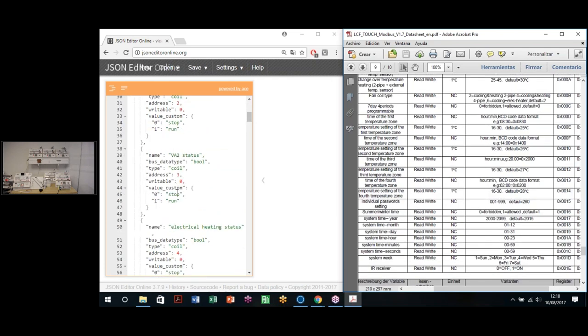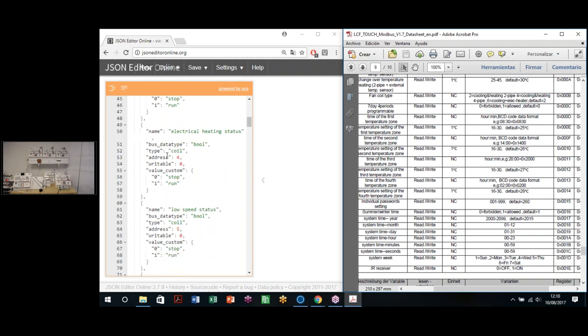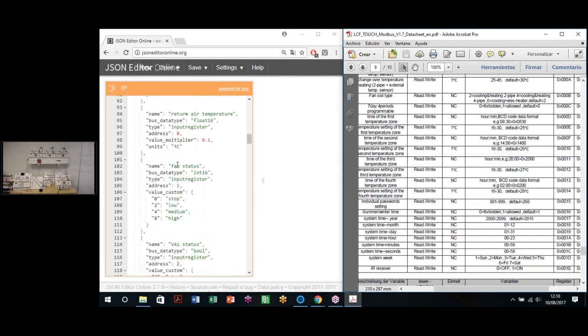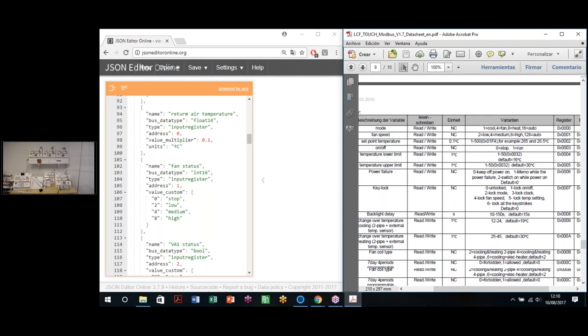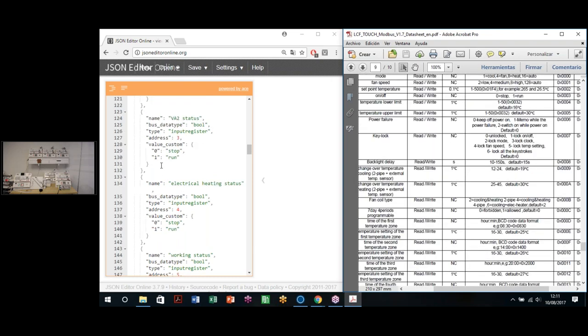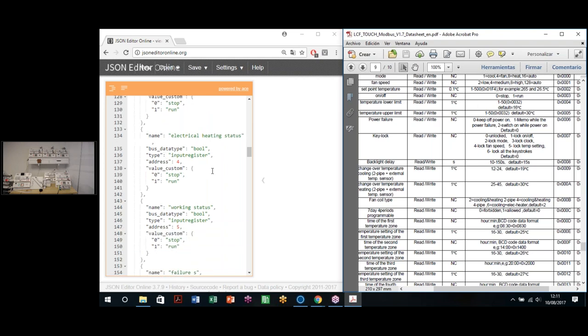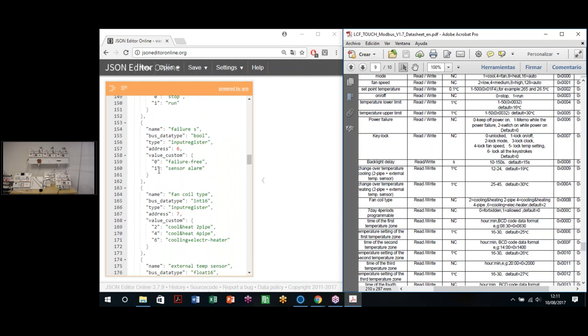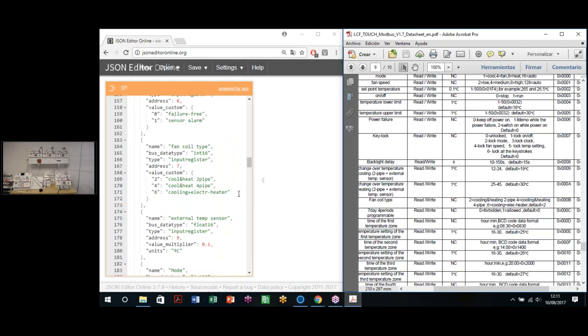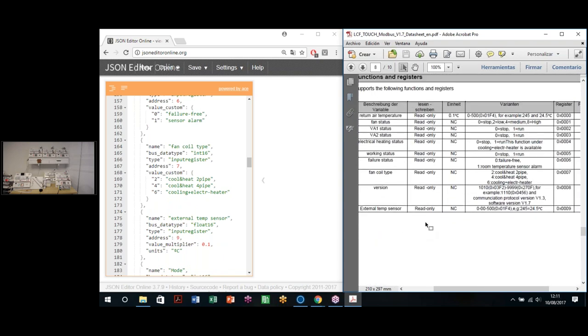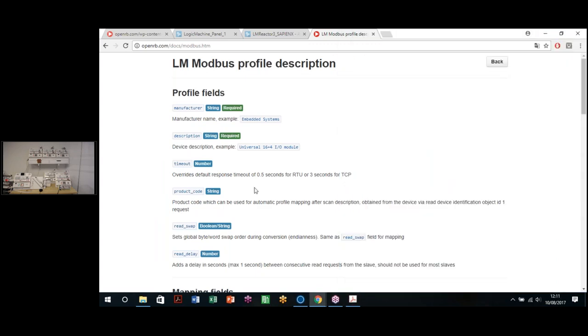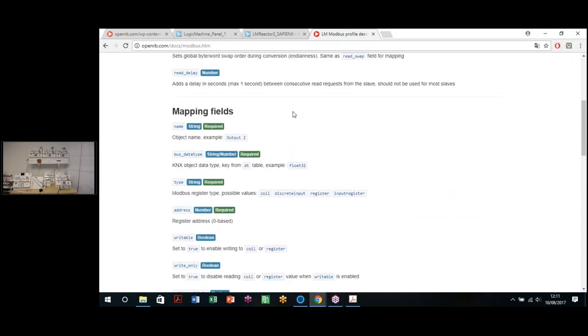Once we've done all this configuration for all the variables, the registers that we are going to use, or if we want, all the registers that we have in the table. Sometimes there are too many and maybe we are not going to use all of them. We can configure just the ones we need. Let me search for an example, I have it here, there we go, fan coil type. If we go to the fan coil type, we can see that the variations of this object can be 2, equal to coil heat in 2 pipes. Here we go. 4 and 6 are different values that we can change in this profile. So once we've created this profile, we can check other options in this document.